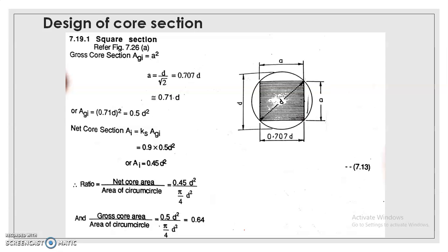the circular cores are invariably used because of their superior mechanical stability, especially under short circuit situation. For circular coils, the shape of the core section has to be selected so that no useful space is wasted and the amount of copper used is minimum. For economy in copper, the core section is such that the length of the perimeter is minimum.